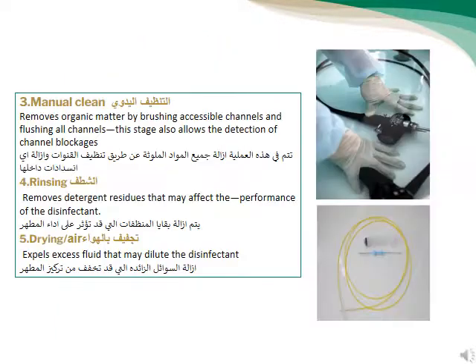Manual cleaning: remove organic matter by brushing accessible channels and flushing the channels. Rinsing: removes detergent residue that may affect the performance of the disinfection. Drying: expels fluids that may dilute the disinfectant, using air.